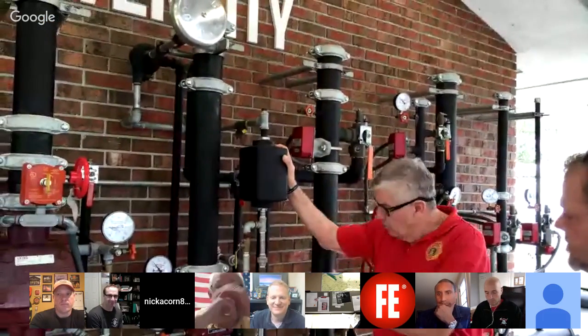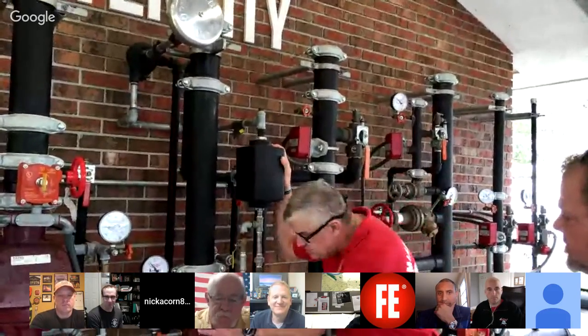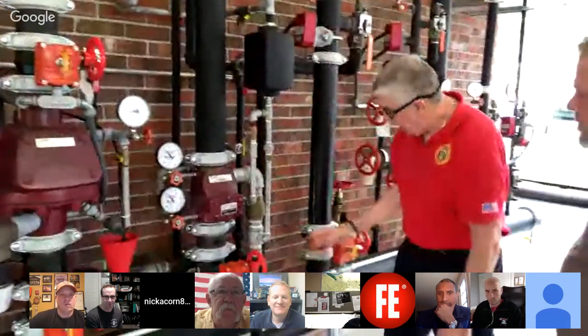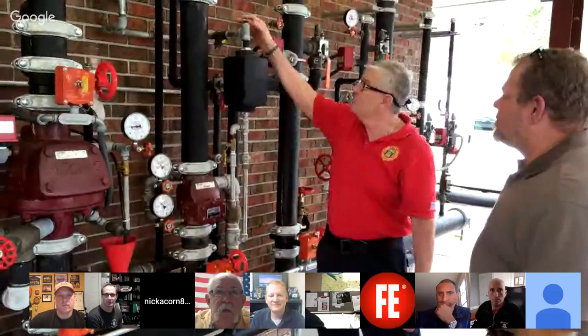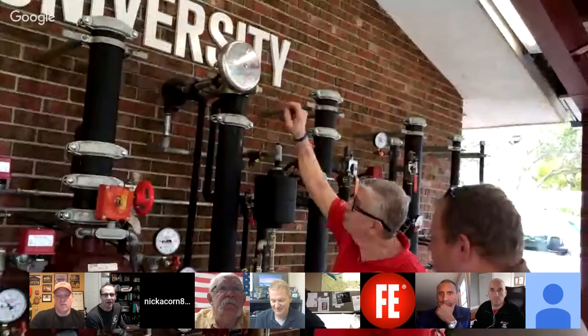Now, this is the kind of system I learned on up in the Chicago area. When I first learned sprinkler systems, it was the alarm check valve. It was an OS&Y. It wasn't a butterfly such as this. And of course, a 2-inch main drain. And we did have this retard chamber that I understand, if it can drain faster than it can fill up, it won't set off. You put a pressure switch here, for instance, to notify ADT or central station. But this is old school, correct? This is an old school water motor gong.